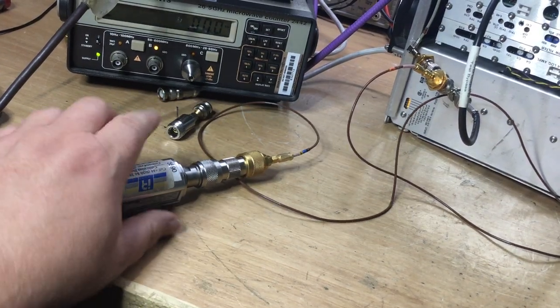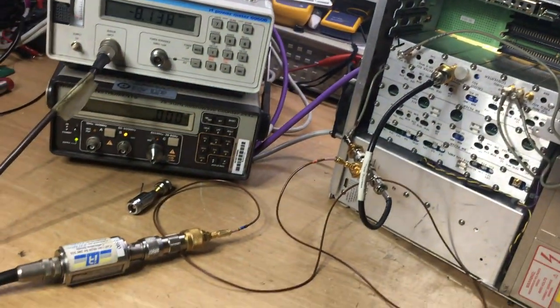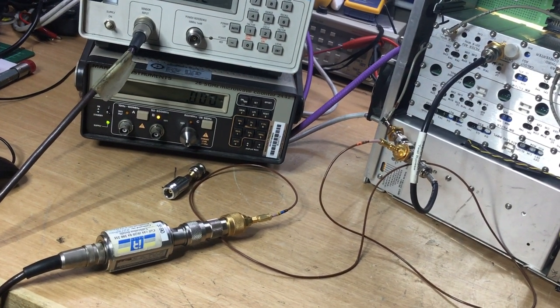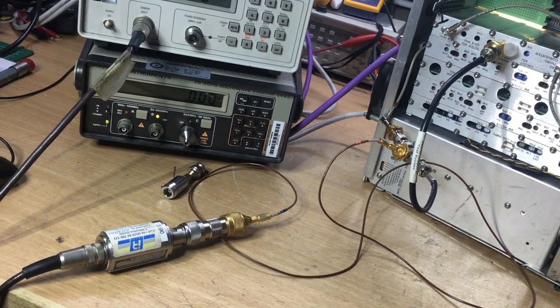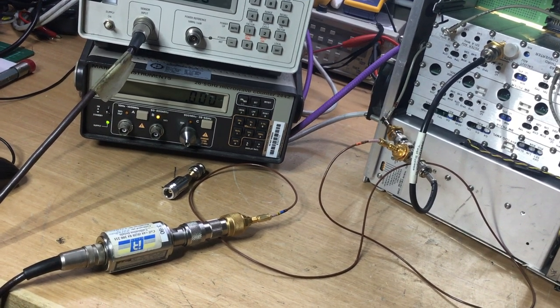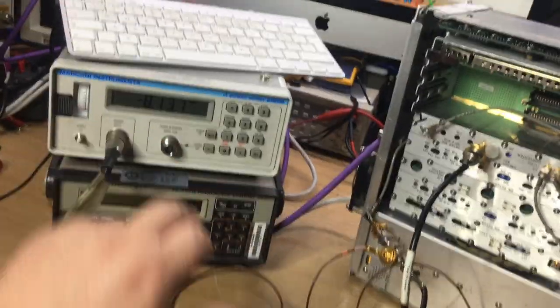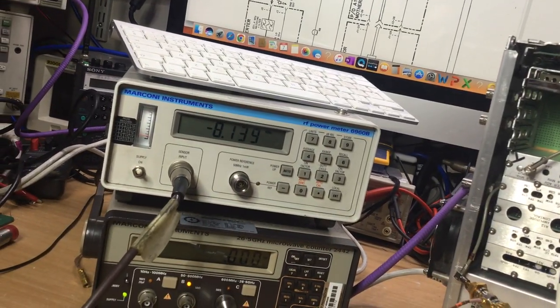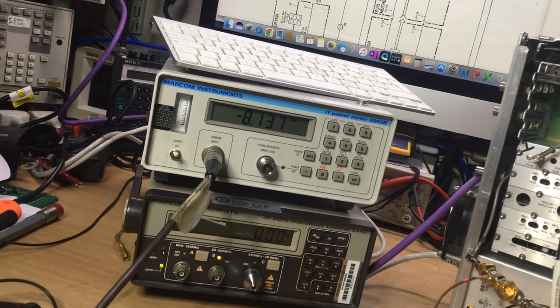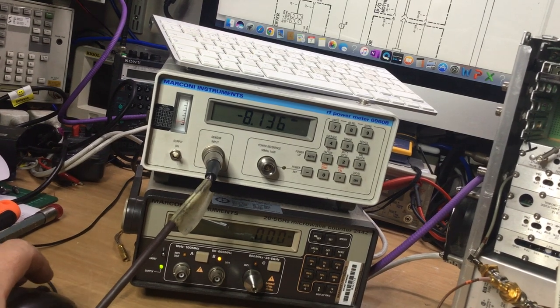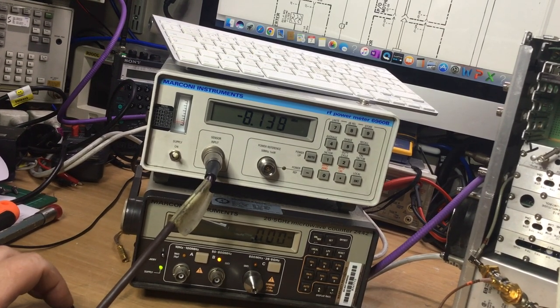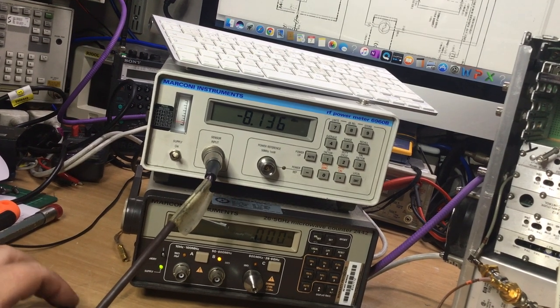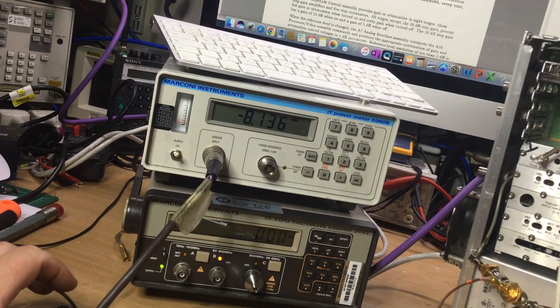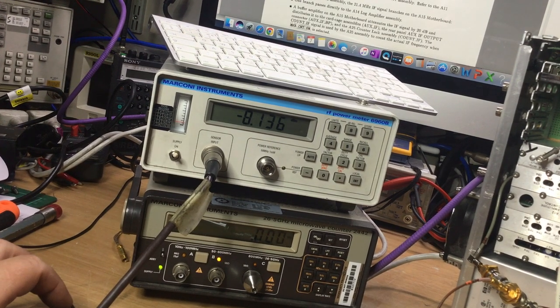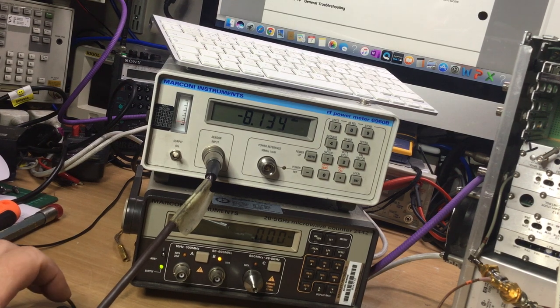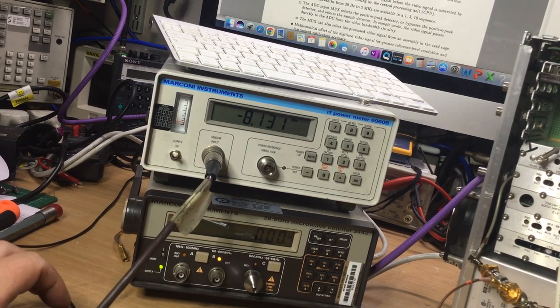Right, we've connected up the output of J3 to the power detector probe, the Marconi RF power meter, the 6960B, which is this instrument here. As we can see, we're measuring minus 8.1 dBm as the RF level. Now, I can't find anywhere in the diagram any reference to what level that should be, but I'm just going to read on now to see where it talks about the levels that should be there and see whether that compares with what it should be. That will give us an indication.